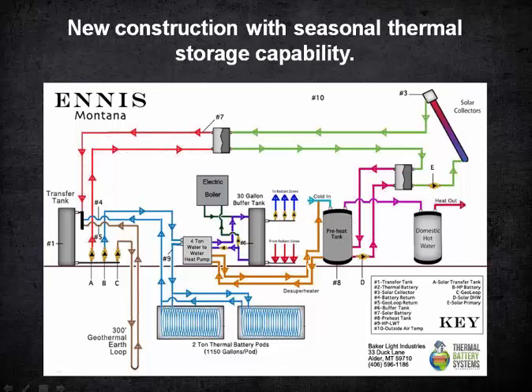Right now that loop, it's not 300 feet, it's 340 feet, so that's a little bit off. And like I said, we've been pumping solar energy down that borehole for 3 months now, and we heated it up to 65 degrees. So if I'm running circulator C and testing the temperature coming back into the transfer tank at that number 5 location, running it all night long, the coldest it gets down to at this point was about 65 degrees.